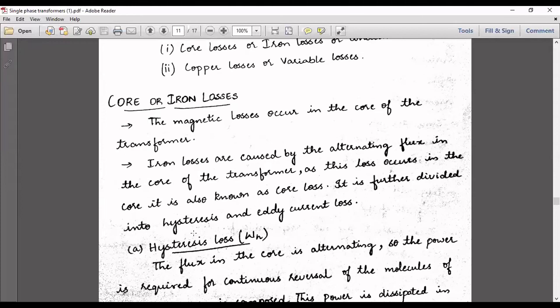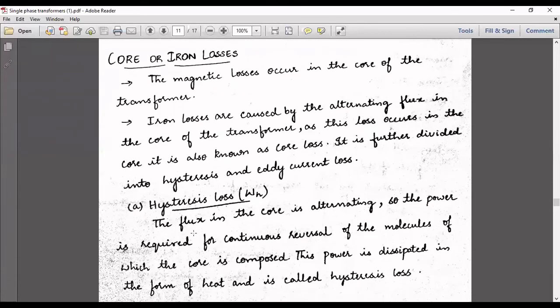These iron losses or core losses are caused by the alternating flux in the core of the transformer. Whatever alternating flux flows in the core of a transformer causes the iron losses. As these losses occur in the core, the name is core losses. It is further divided into hysteresis and eddy current losses. Why is it known as constant loss? Because it does not vary. Once we get the core losses, they always remain the same. Therefore, it is also called constant loss.